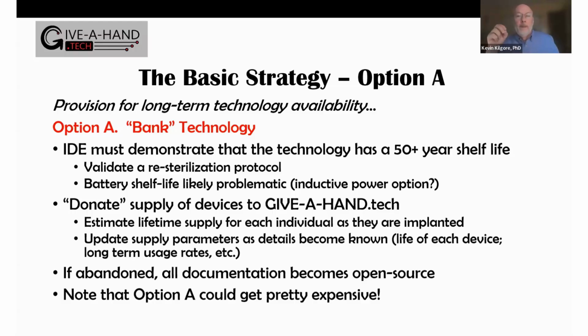The problem there is, first of all, sterilization is a real issue. There's no such thing that I know of as sterilization that has a 50-year expiration time, although that would be fantastic. So you'll have to re-sterilize, or have a sterilization protocol that you implement 50 years from now. That's definitely a challenge. Batteries are probably shelf-life limited, at least as far as I know. All batteries are going to have some lifetime after which you're not going to implant that device. You've got to replace it. So maybe you have to have an inductively powered option where you don't have the battery inside the device, and you run it from an inductive link. Those are options, but each one of those, of course, carries a certain cost with it.